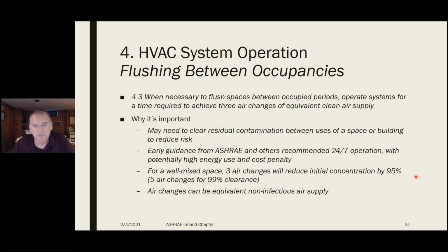And considering just a perfectly mixed space, 3 air changes will result in 95% removal. This can be adjusted for other targets. 99% takes 5 air changes, and you can adjust this for ventilation effectiveness as well. And you may have seen that there's now a tool available in the building readiness guidance from ASHRAE that allows you to take all of those things into account.